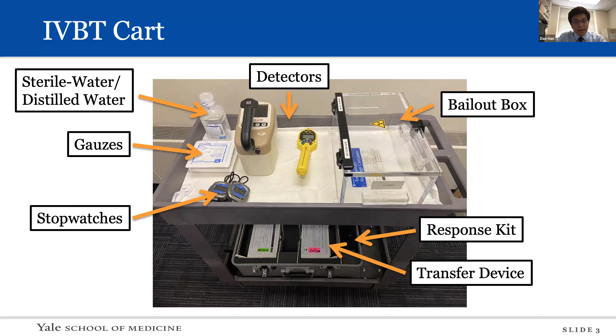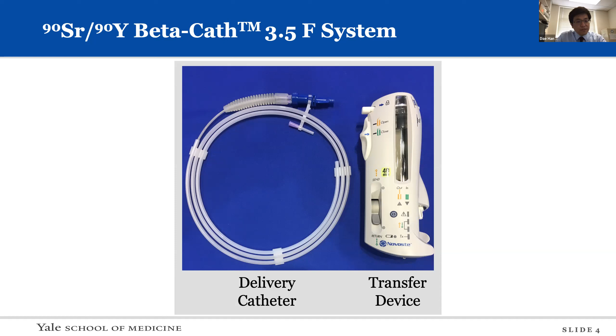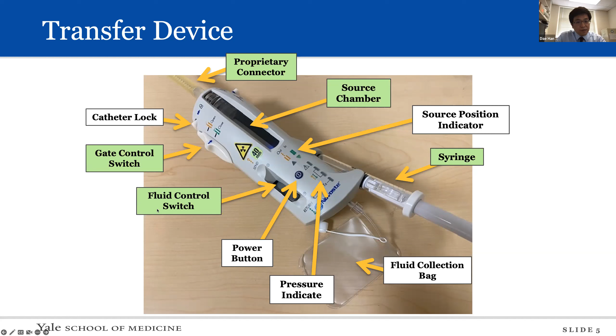These are the delivery catheter and transfer device. The transfer device includes the radiation source, and then the source will be delivered to the treatment lesion through the delivery catheter with hydraulic pressure. So to deliver the source to the treatment lesions, the delivery catheter needs to be attached to the transfer device, as you can see in here. And also a water-filled syringe provides water pressure, and the fluid collection bag collects the returning water. And the gate control switch controls the source chamber gate, and then the fluid control switch controls the water flow directions, which is forward and backward.